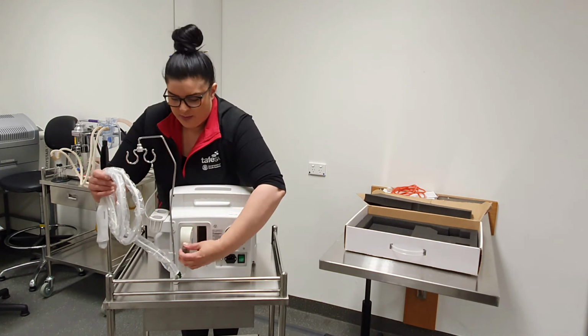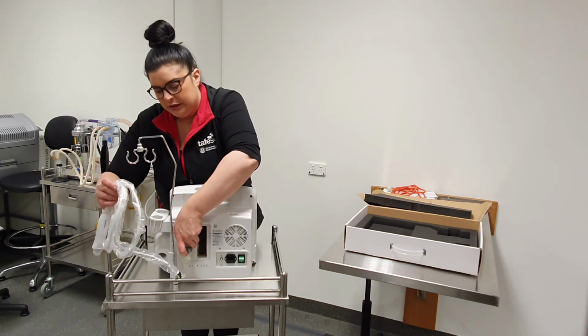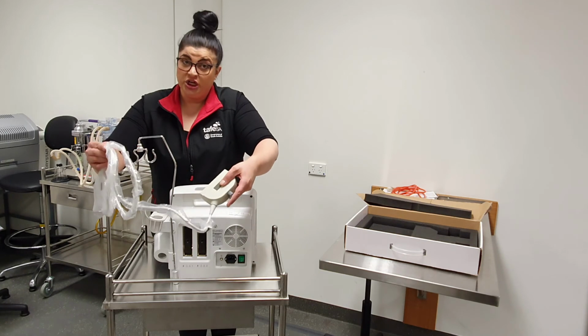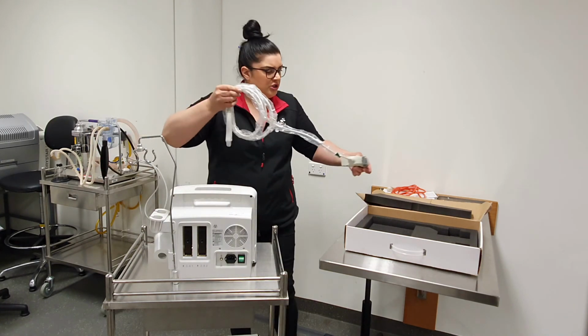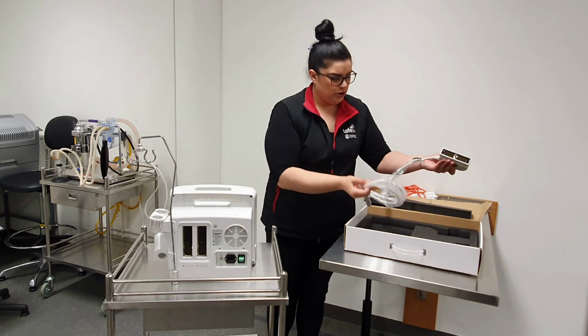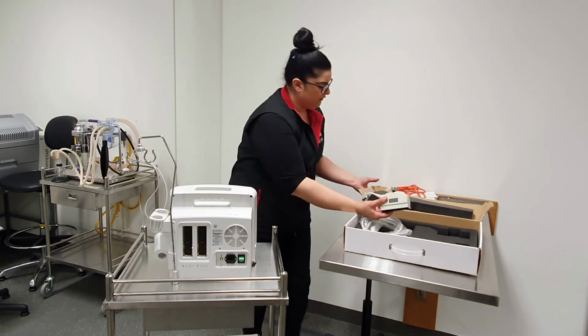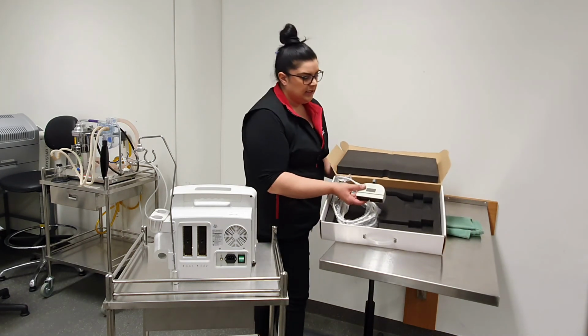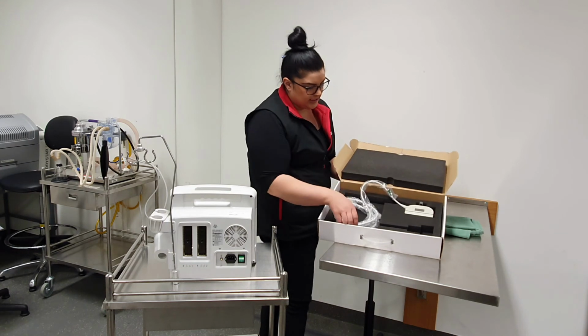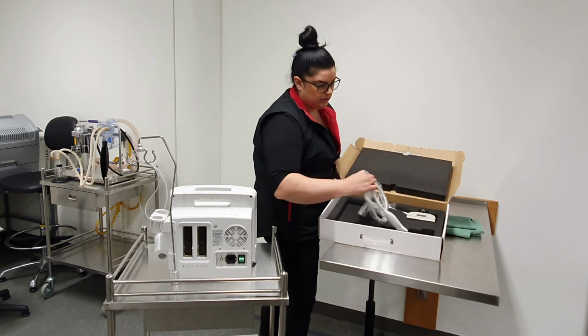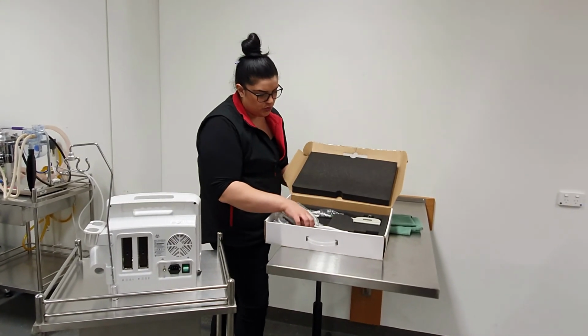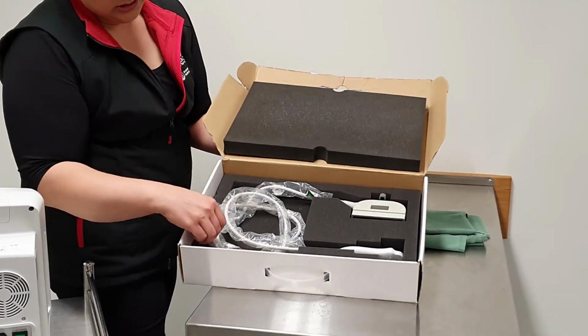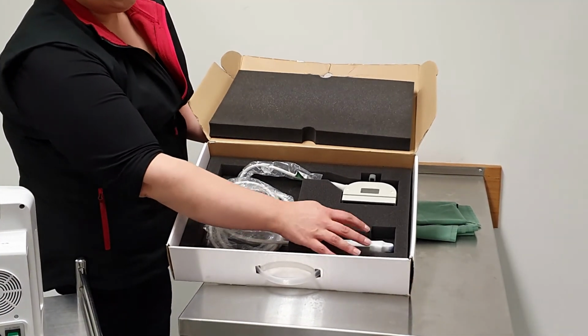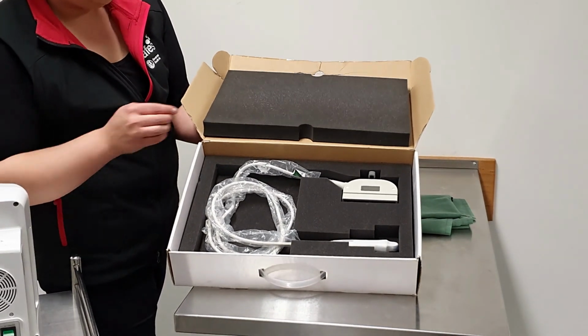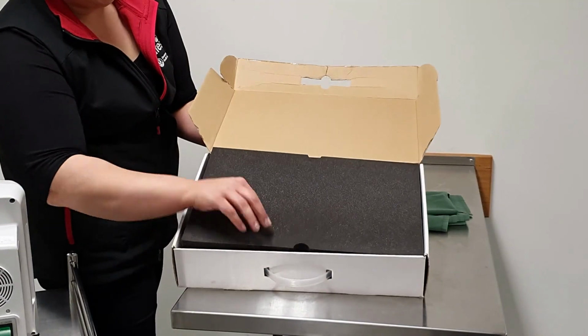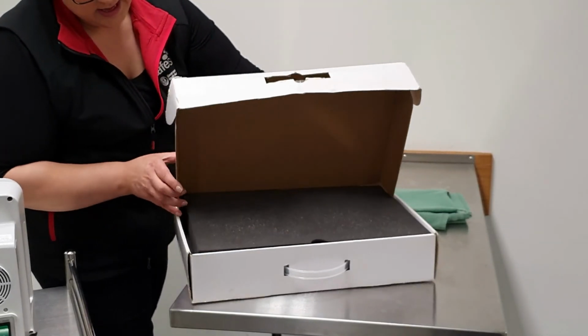All right, so I'm going to take a hold of my probe here, undo the turn lock, remove the socket from the machine. We're going to assume that I've cleaned it as per manufacturer's instructions. And I'm going to put this back into the cutout holes here in the foam. So I'm going to gently lift this while I do it so you can see. So you can see there that the socket fits quite nicely in there. I'm going to just turn this over so that we've got gentle curves in our cord. And that'll sit nicely in there, and I've got the probe sitting here in the other cutout hole of the foam. And we pop the protective layer on top and pack this away.